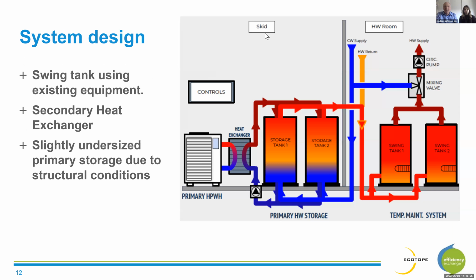So the system design itself is essentially set up in what we call a standard swing tank approach, which is the heat pump used to heat primary storage upstream of a temperature maintenance tank. That temperature maintenance tank is getting the recirculated hot water and maintaining the water hot in the building so that it's delivered to the tenants quickly at temperature.